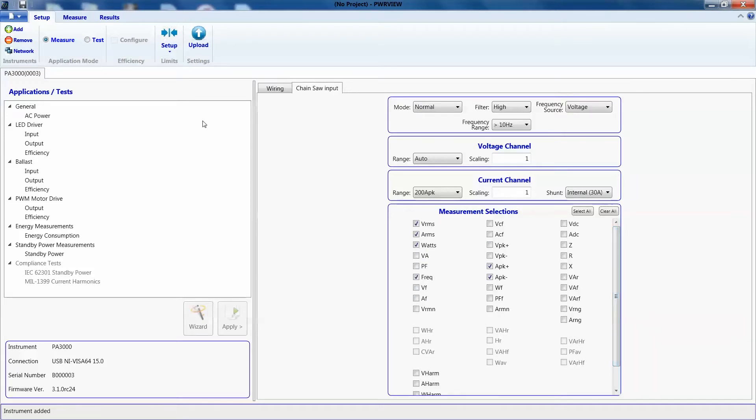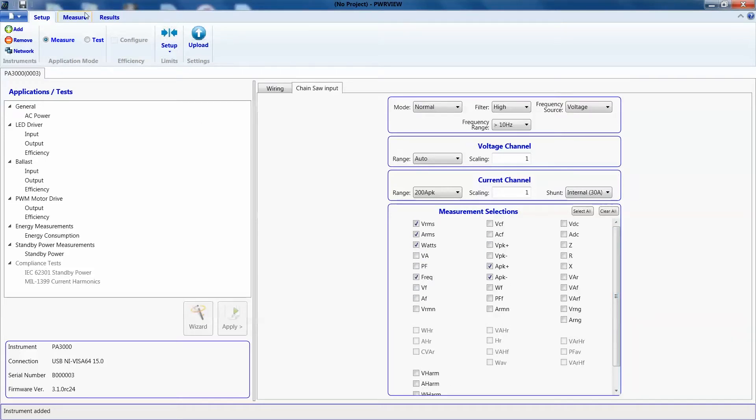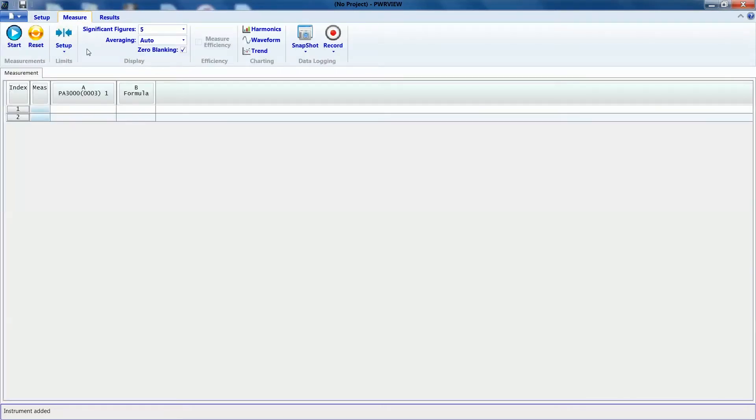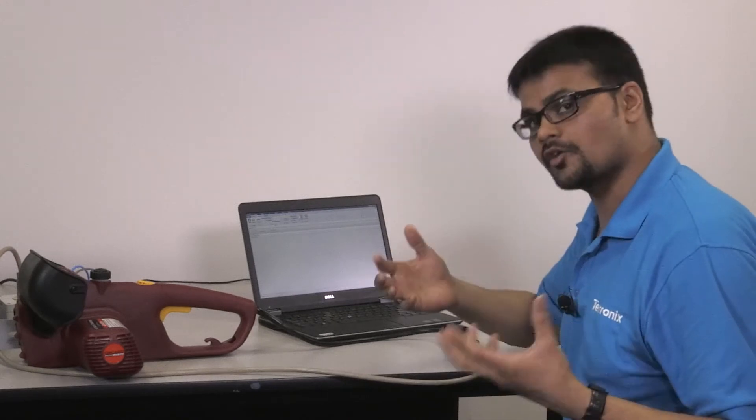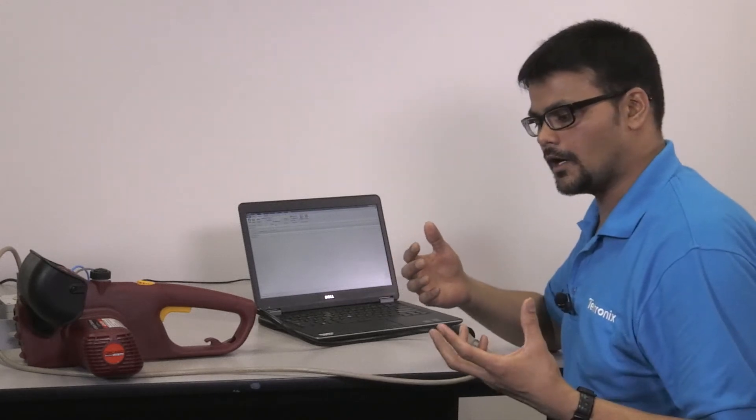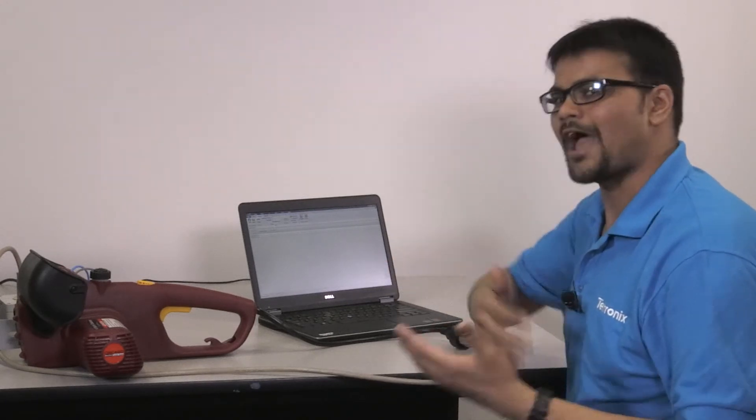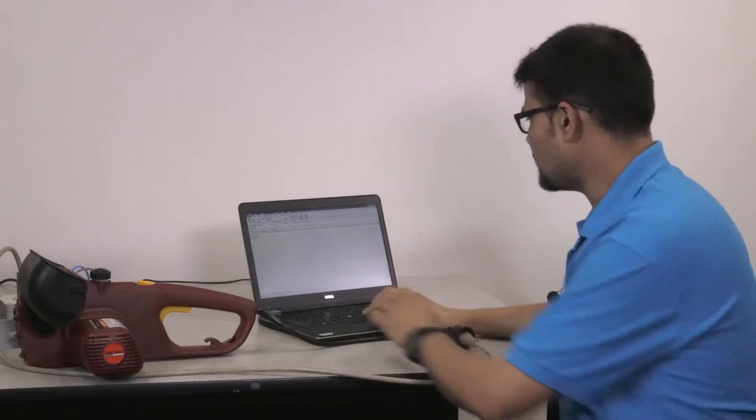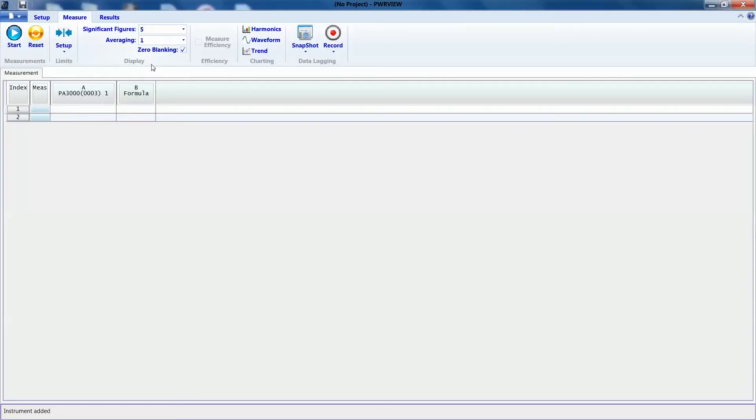Let's go to the measure page. This is right here. We'll get rid of the averaging again. As I said, because we are measuring inrush current, we don't want to average those results. We want the instantaneous inrush current.